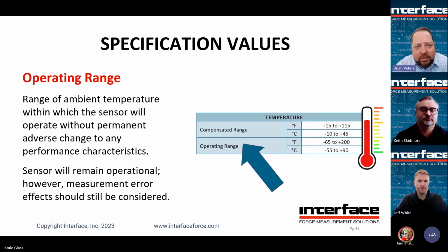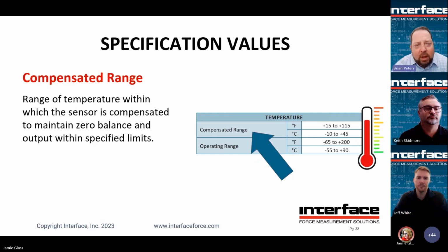Operating range is as expected. This is the temperature range that the sensor can be operated in without any damage or anything that would be long term. Now, pay attention that just because it has an operating range, you may see some error influence as the load cell or sensor is subjected to varying temperatures within that range. And so that's the next part here. So the next slide. Compensated range.